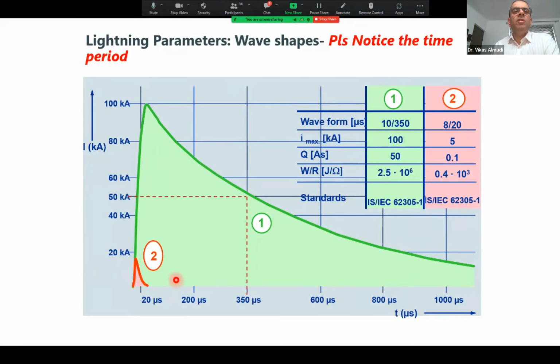So when we talk about lightning, we always talk about 10/350. When we talk about surge, we talk about 8/20 microseconds. Lightning can be a source of surge. And here we have to see that in both cases, the rate of change of current, di/dt, is very, very high.